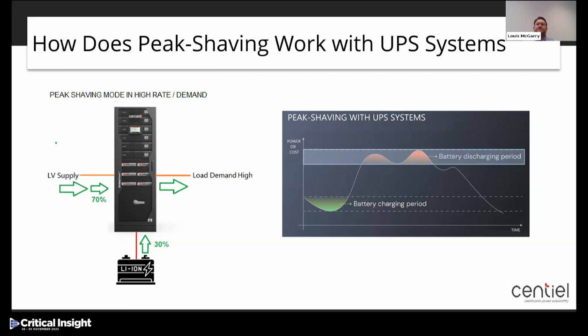It's important to note that if a UPS system is supporting critical loads, enough autonomy must be left in the system to support that sensitive load in the event of a power disturbance or a power failure, allowing the load to be safely transferred to a secondary source, such as a generator, or to be gracefully shut down.